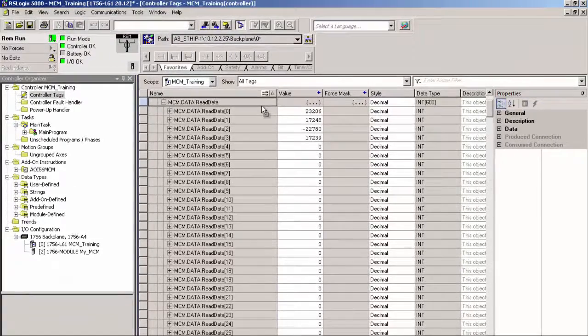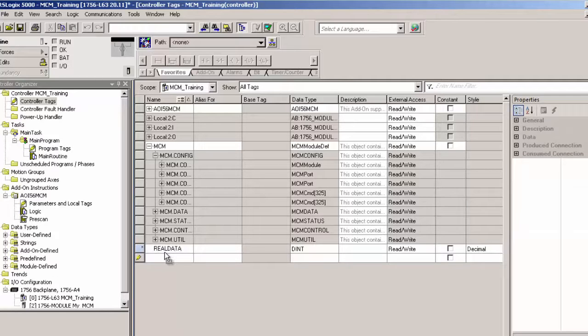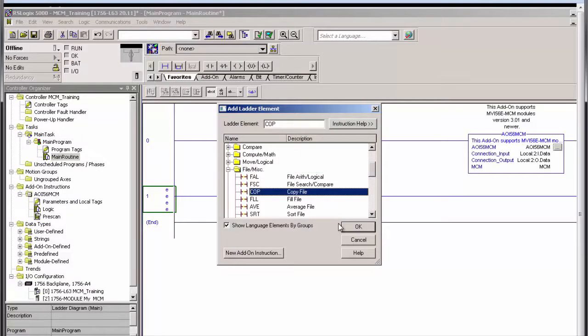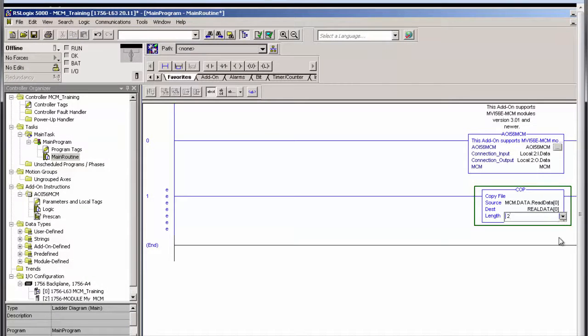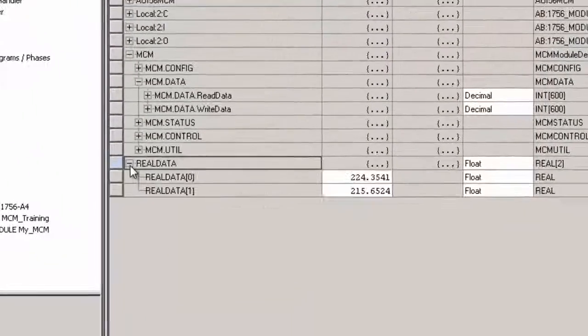To see the data as the floating point values they started out as, they must be copied into two tags with a real data type. This is accomplished in RSLogix 5000 by adding a copy instruction to the main routine ladder. This will take the four 16-bit words we read from the slave device and combine them back into two 32-bit floating point numbers.